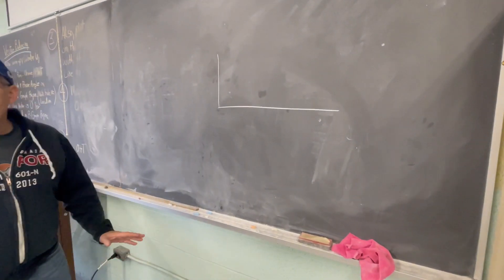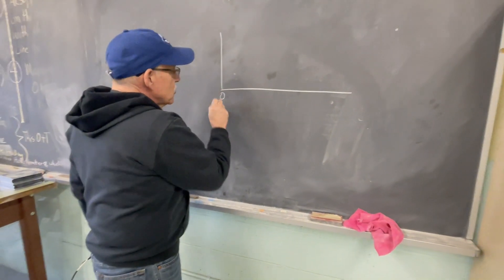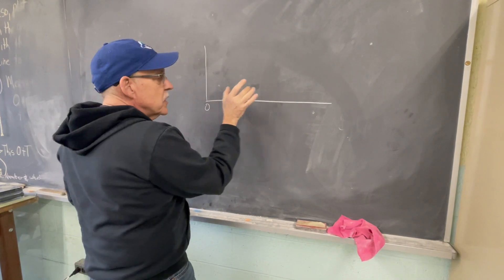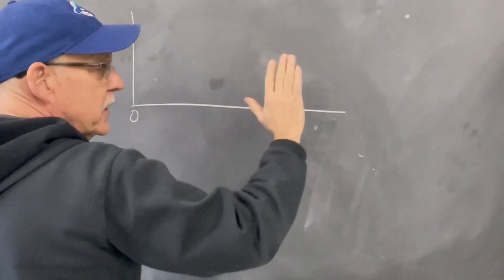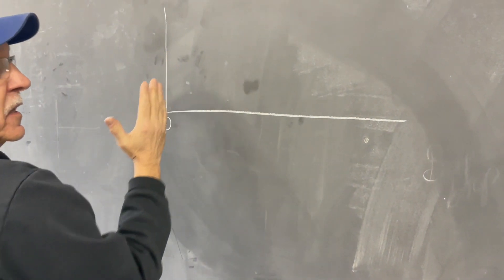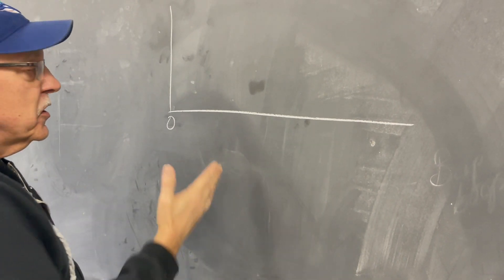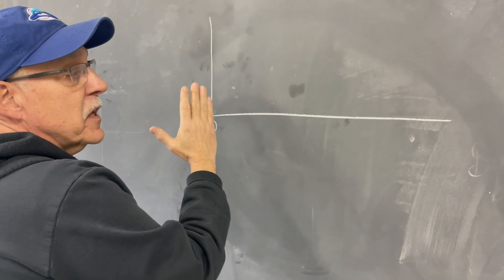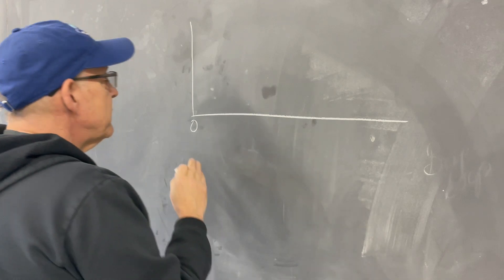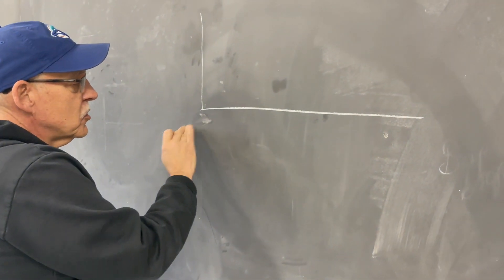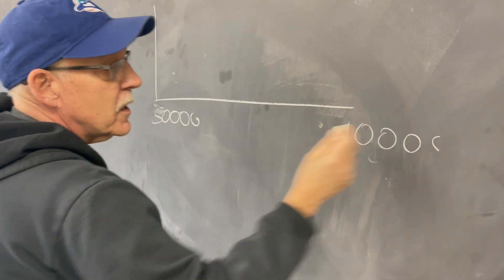When setting the F-max, the F-min means zero — so what we're doing is setting the span of our spectrum. The reason we do that is because certain faults happen at certain areas on the spectrum. High-frequency faults and early bearing issues happen out on the right side of the spectrum; imbalance and things related to turning speed happen on the left side. We can segment this and set the F-max at anything we want — for example, 50,000 CPM up to 100,000 CPM.